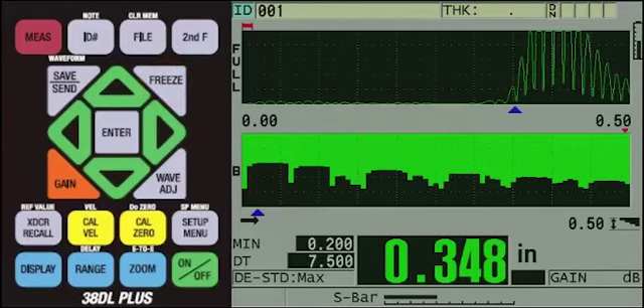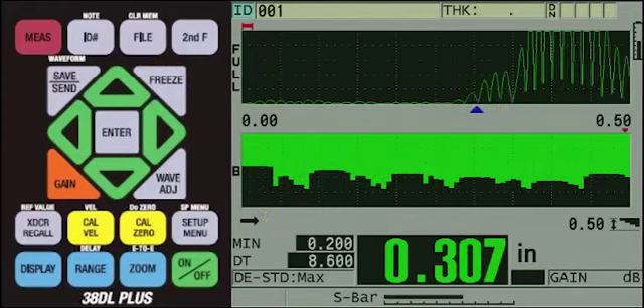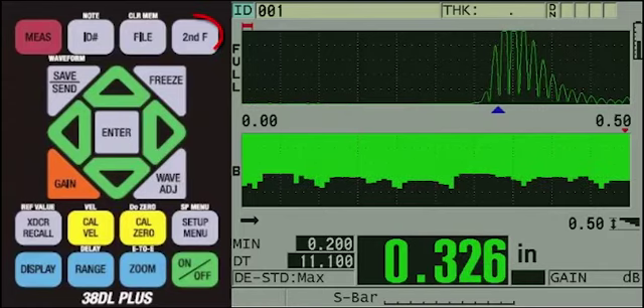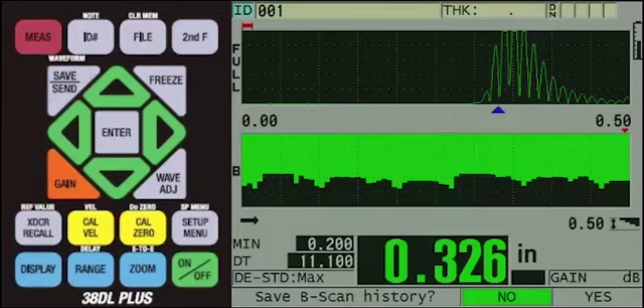Once the scan is complete, we can save it by first pressing and releasing the second F key and then pressing the Save Send key. If the scan goes beyond the instrument display, you will be asked if you want to save the B-scan history, which includes the portion of the scan that is no longer on screen. In most instances, you will use the right arrow to highlight Yes and then press the Enter key. The encoded B-scan has now been saved to the instrument's internal data logger.